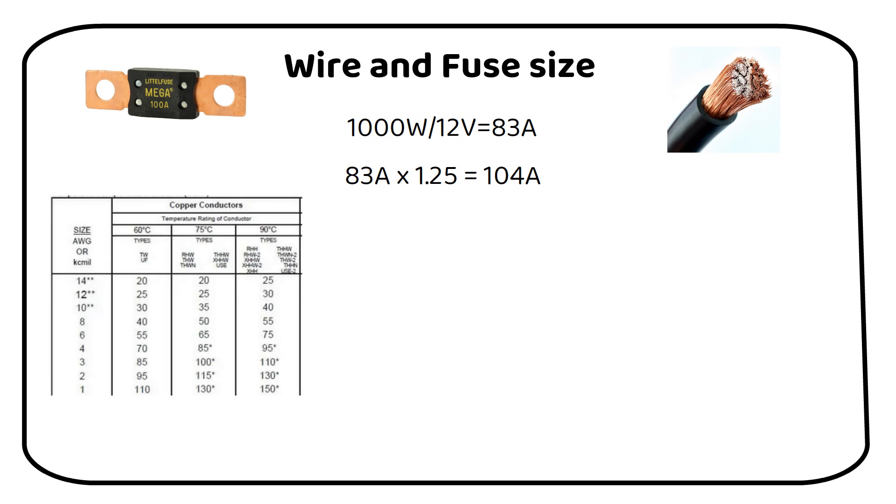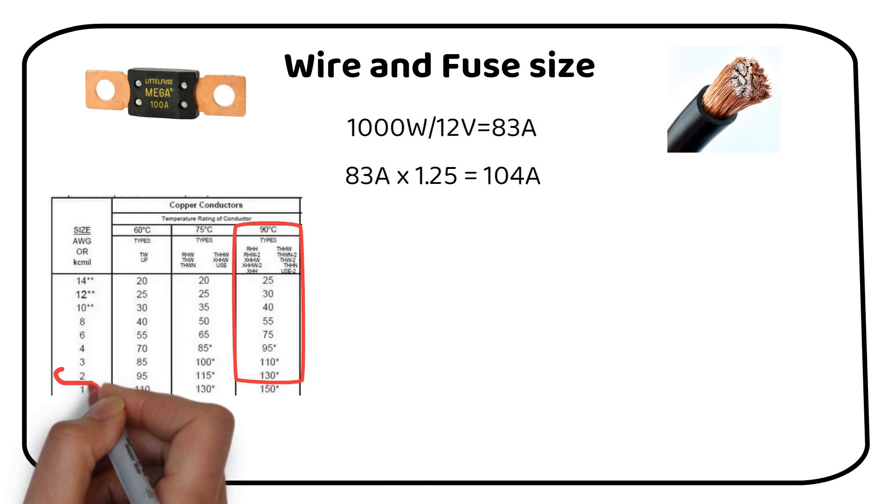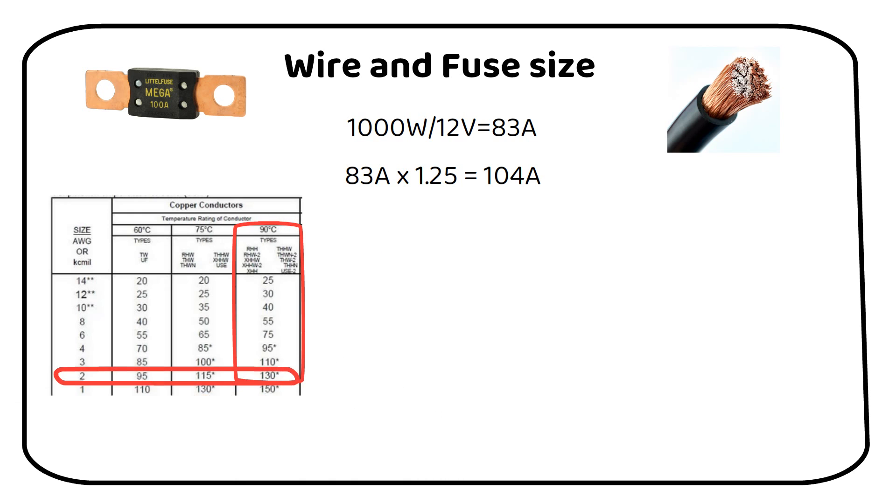We need to select a wire capable of handling this current. Since a 3 gauge wire isn't readily available, we will choose a 2 gauge or 35mm square wire with a 90 degrees Celsius insulation temperature rating.